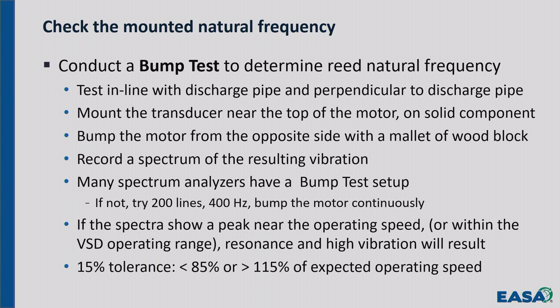Okay. Usually you mount the transducer up near the top on some solid component, not on the fan cover, not on a shroud or something. And you bump the motor on the opposite side with a mallet or a block of wood. Don't use a sledgehammer or anything hard. Don't use a dead blow hammer. You want the hammer to bounce off when you strike it. A dead blow hammer would stick to the part. So use something with a soft enough face that you can bounce it off, and it'll sit there and vibrate, and you're going to get a real nice spectrum on your spectrum analyzer.